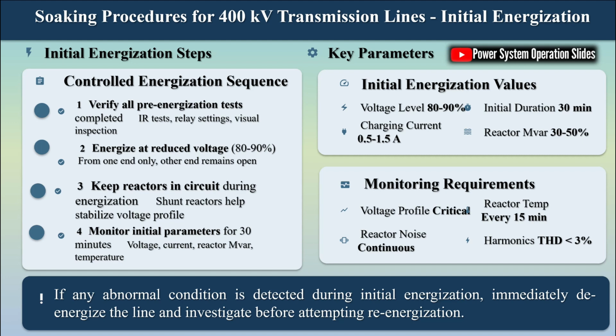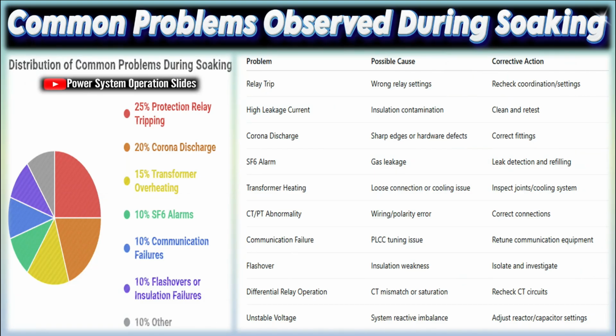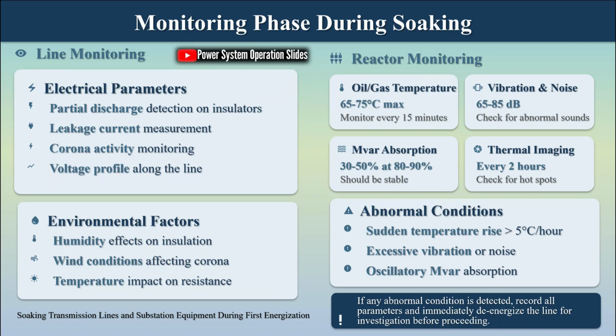The transformer is typically energized without load during this phase, minimizing thermal stress while enabling careful observation of electrical behavior. This process also allows magnetic circuits and winding structures to settle into normal operating conditions before the transformer is subjected to load currents and full system voltage.